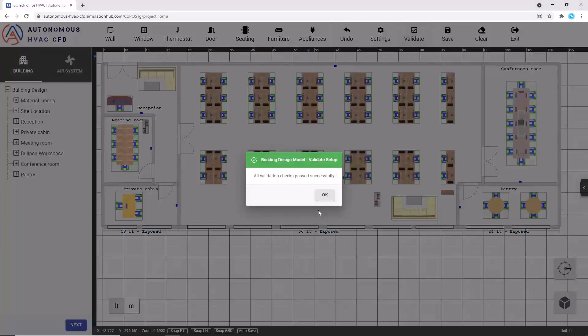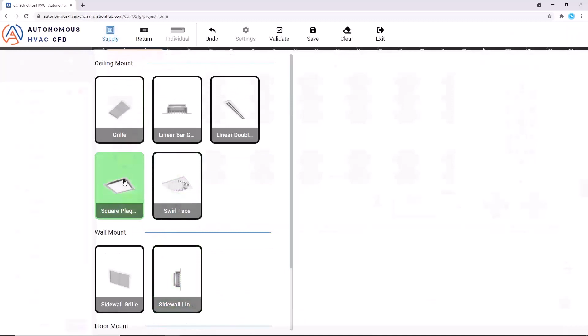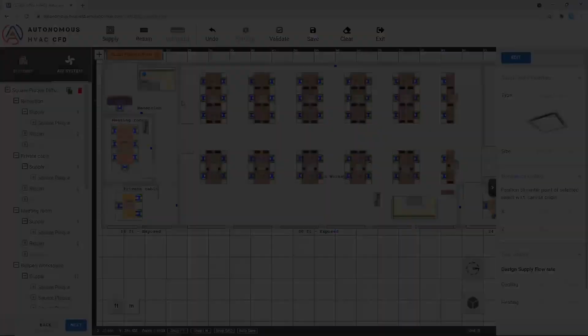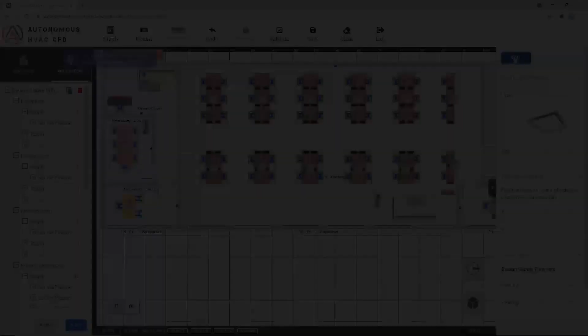After geometry validation checks, we can move to airside system to design space air distribution. Now we are creating a ducted air conditioning system with square plate diffusers. From the diffuser component library, select the right diffuser type and size. For this case, I am selecting square plate ceiling diffuser of 24 in size and placing them in appropriate locations. Now for each diffuser, we should specify the designed supply CFM based on the cooling and heating load calculations.